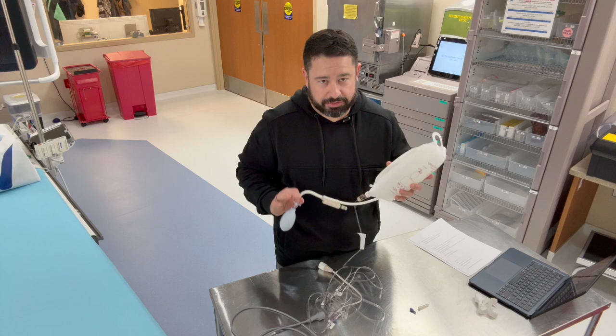That's 300 millimeters of mercury. That's important. Why 300? Because that gives us enough pressure to overcome the pressure inside of the patient. So the standard is 300, and that's what the green mark takes us to. So now we're going to take our pressure line and get the air out of it.